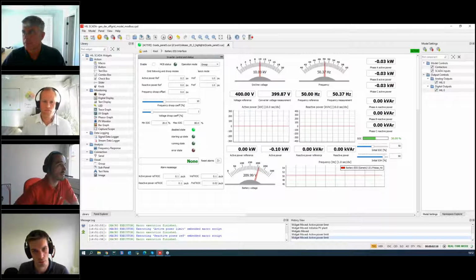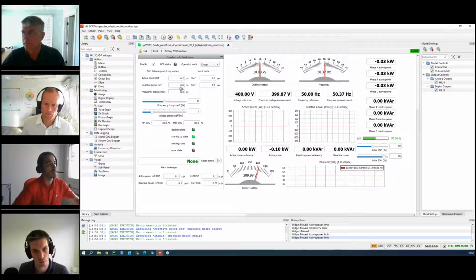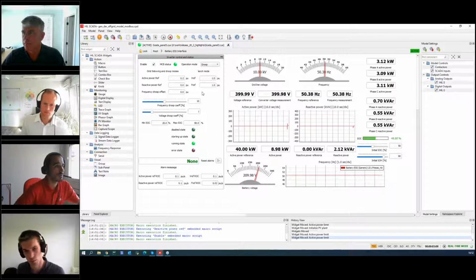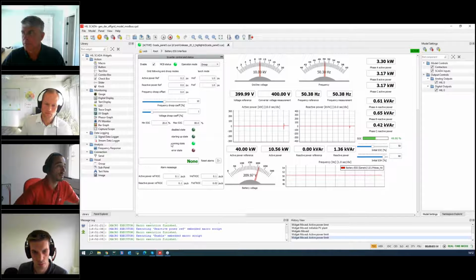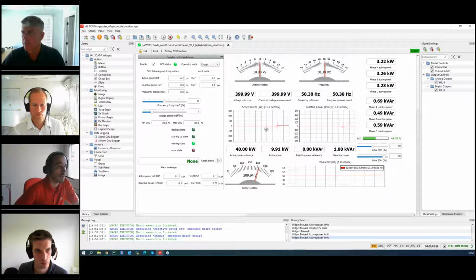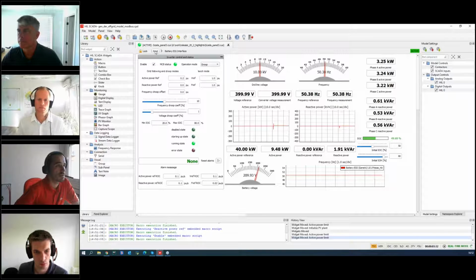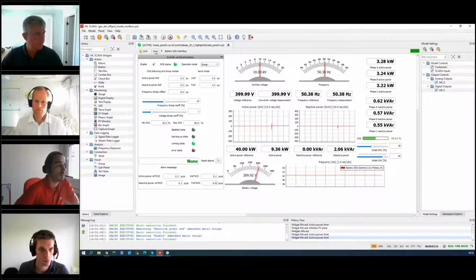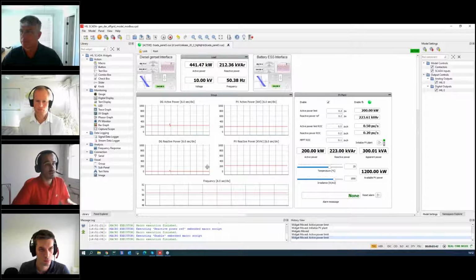Now we will start the interesting part, for example starting the battery in droop mode. So the battery will be working in parallel with the diesel genset in the droop mode of operation. Now we see that our state machine, our DR, is in the running state. We had some transient here, and we can see that the battery is supplying the load with almost 10 kilowatts. The frequency is now a little different than previously, but this is also expected because now we have two DRs in parallel with different droop characteristics. We observe some changes here.